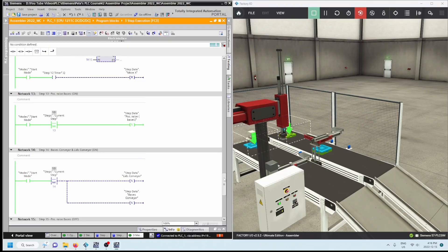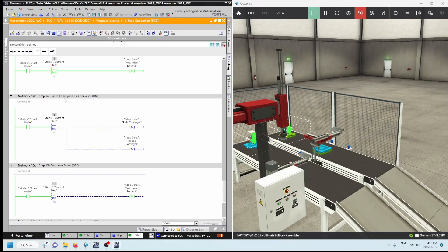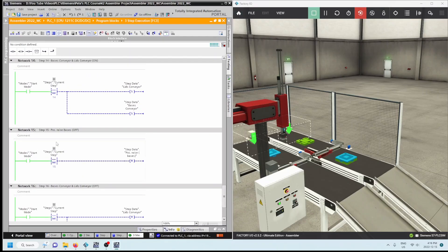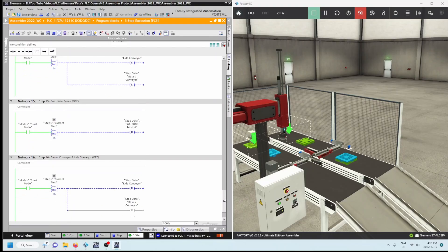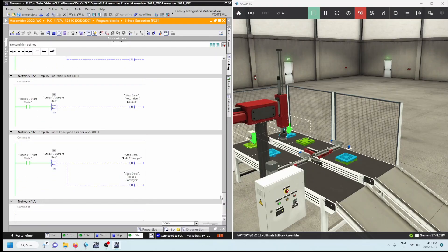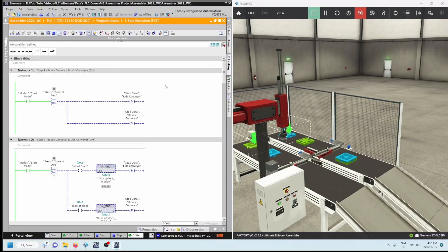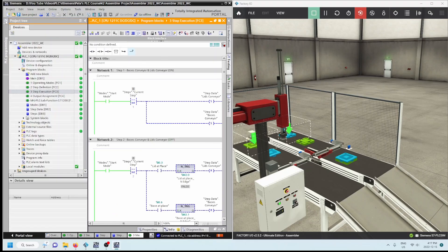Step fourteen: base conveyors and lid conveyors both turn on. I didn't want the operator to click multiple times to get the timing right, so the next steps happen on their own. The pos. raise bases went off, it dropped down, then base conveyors and lid conveyors turned off — that's everything in our step execution. I was going to go through this slowly one more time, but you have a PDF printout of the PLC program in this final section of the course — scroll down or print it out to see the step execution in detail.